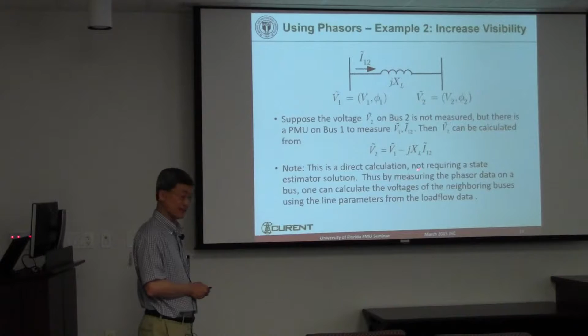For people interested in dynamics, you can look at oscillation. Say you have a transmission path from one end to the other, bus 1 and bus 2, with a disturbance on it — you measure the frequency at each end. We're not talking about generator angles here, because in general PMU units aren't inside the generating station. The frequency difference actually shows the inter-area oscillation between the two points. It's not as good as rotor oscillation, but good enough. There are 30 samples per second, and this oscillation is between 0.25 and 3 hertz, so there's plenty of bandwidth to see it.